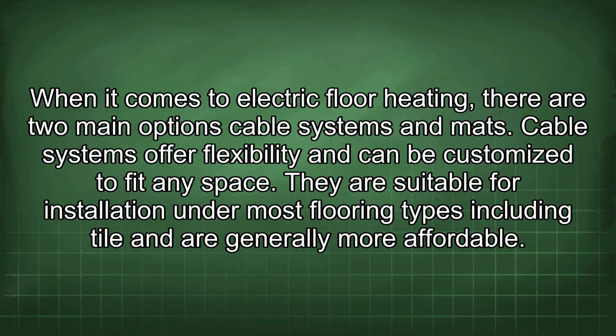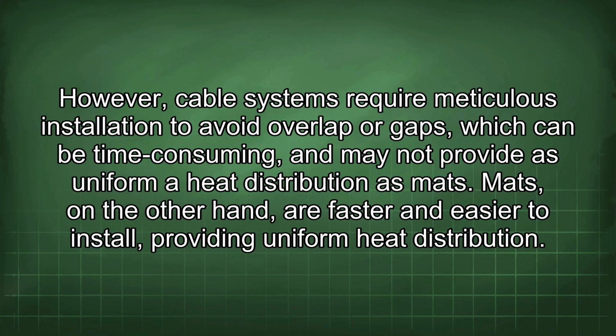When it comes to electric floor heating, there are two main options: cable systems and mats. Cable systems offer flexibility and can be customized to fit any space. They are suitable for installation under most flooring types, including tile, and are generally more affordable. However, cable systems require meticulous installation to avoid overlap or gaps, which can be time-consuming and may not provide as uniform a heat distribution as mats.